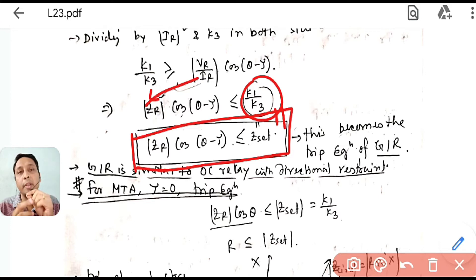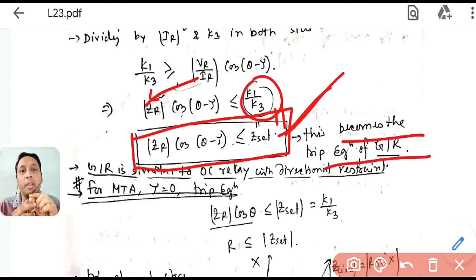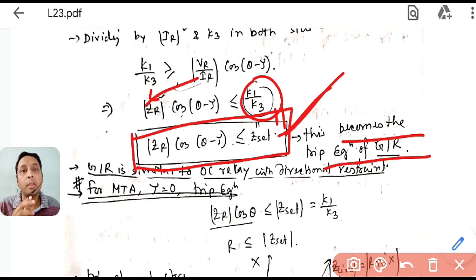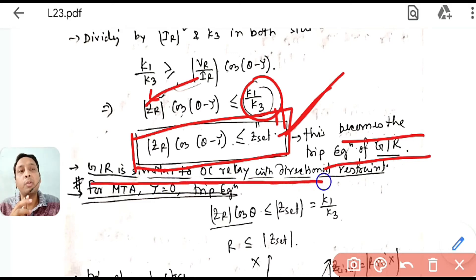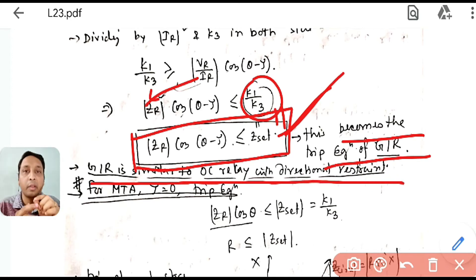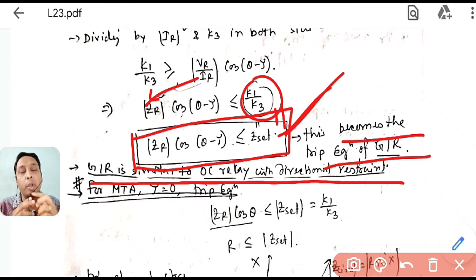This becomes the trip characteristic of the Generic Impedance Relay. Generic impedance relay is similar to an overcurrent relay, but the restraint here is a directional restraint. In SIR it was also overcurrent-relay type but the restraint was due to voltage; here it is directional restraint.